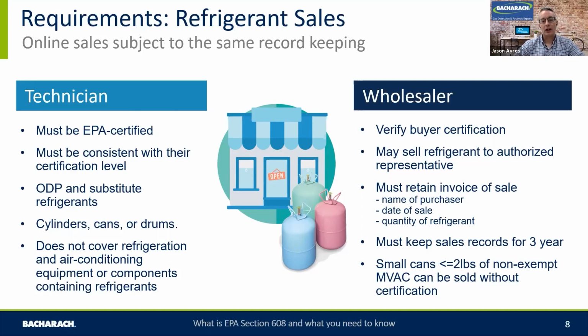As I touched on at the start, record keeping is very important under EPA 608, and for the refrigerant wholesalers and sellers, you must keep records for 3 years and have these available. Again, there's some critical information that needs to be held. First of all, it should be an invoice saying who you sold it to, when you sold it, and the quantity and the amount of refrigerant that's sold. Again, this could be for online sales as well as physical sales within your location. Certain types of canisters and small systems are exempt from the regulations, especially in the motor vehicle industry as well.